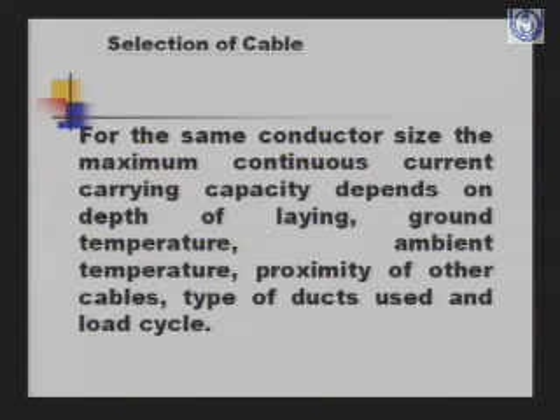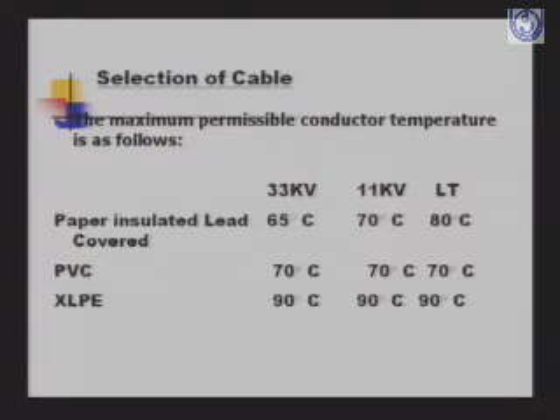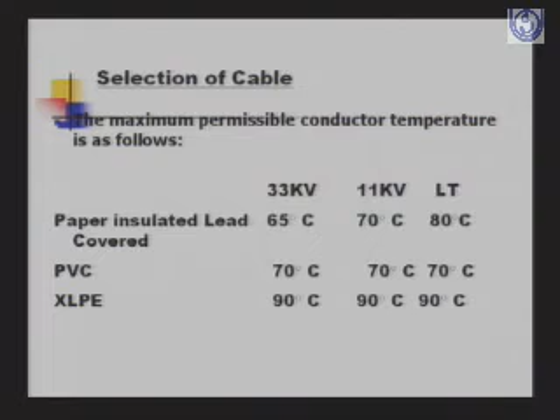So the maximum permissible conductor temperature for various types of cables: for paper insulated lead covered, that is PILC, it is 65 degrees C in case of 33 kV, 70 degrees centigrade in case of 11 kV, and 80 degrees centigrade in case of LT. For PVC cables, it is 70 degrees centigrade in case of 33 kV. In case of 11 kV, it is 70 degrees centigrade again, and for LT also it is 70 degrees centigrade. For XLPE, it is 90 degrees centigrade for 33 kV, 11 kV as well as LT.